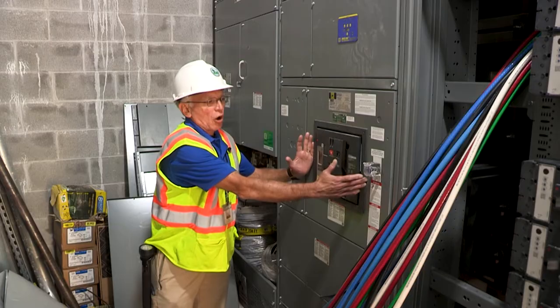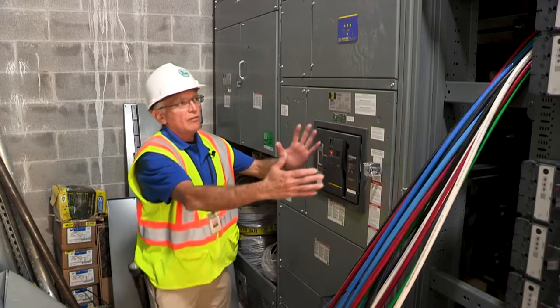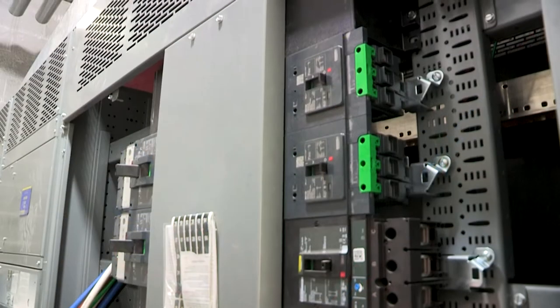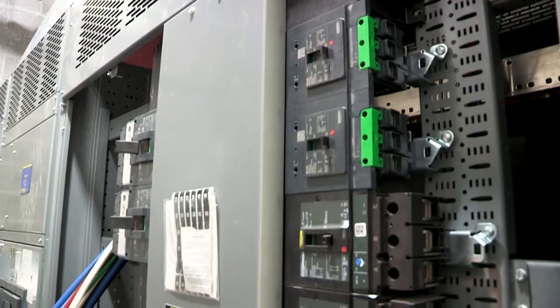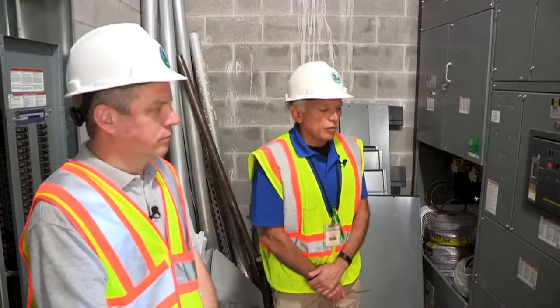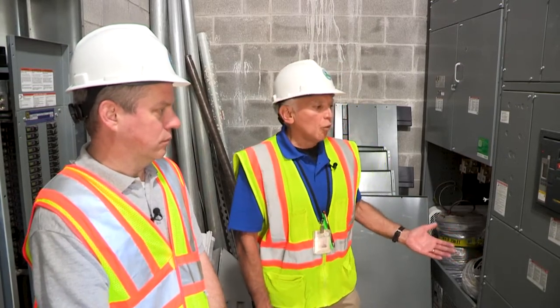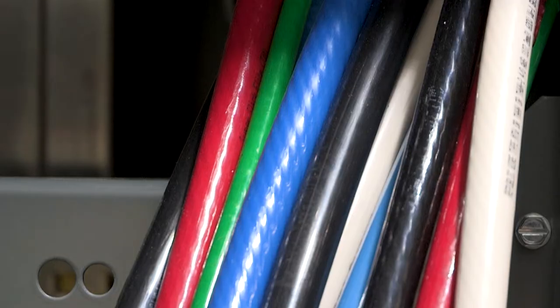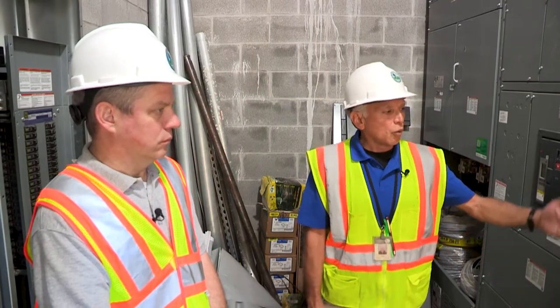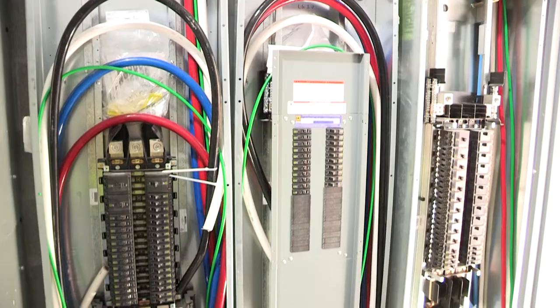This represents our main breaker for all the electricity going to all the other panels in the building — really what we have is what somebody would find at home in their own circuit breaker panels, except these will be feeding other panels. We run everything back to the drawings and specifications for the project. We'll be looking at the wire sizing and wiring material — whether the engineer has specified aluminum conductors or copper conductors — checking everything from conductor sizes and grounding sizes to their attachment points within the equipment.